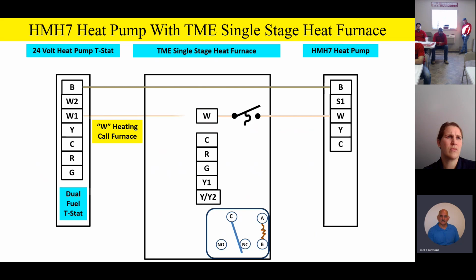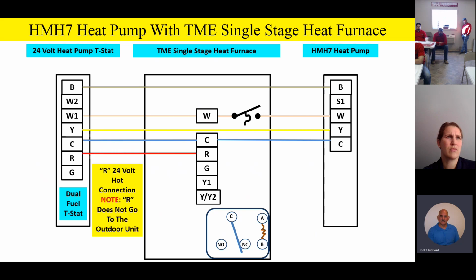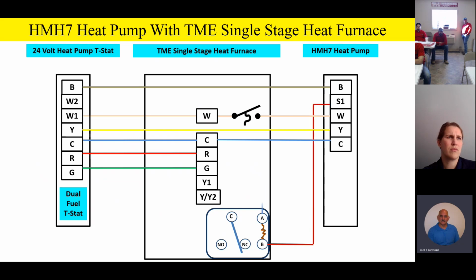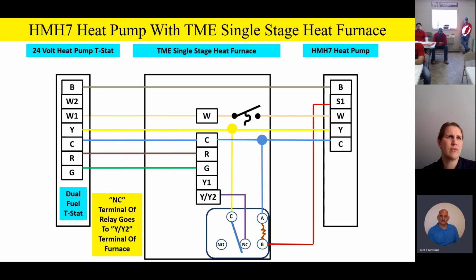As far as the wiring, like I said, it's going to look real familiar to you. We just did this. It's essentially the same wiring we did on the AE air handler, wire for wire. You'll notice that the relay hooks up the same: common and B, or I should say common and the other side of the relay coil. Common of the switching contacts goes to Y, just like we had before. Your normally closed contact's going to go to second stage airflow. Your normally open contact's going to go to first stage airflow. So basically, this wires up just like that AE air handler. It's essentially the same block wiring that we just discussed. It's just on a furnace now, and we have a dual fuel thermostat.